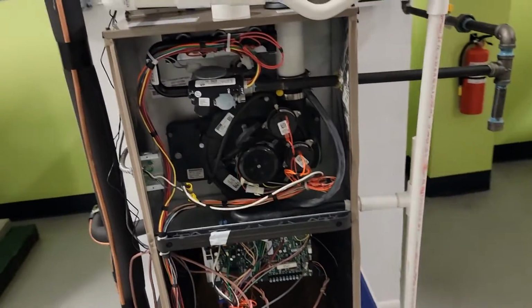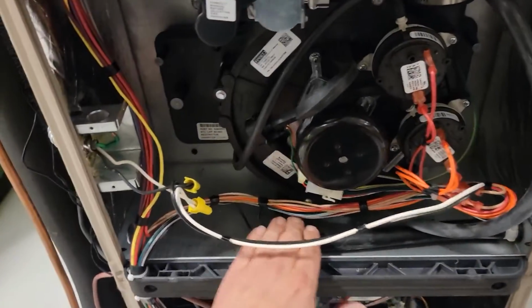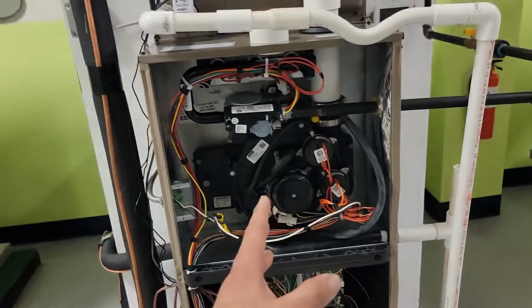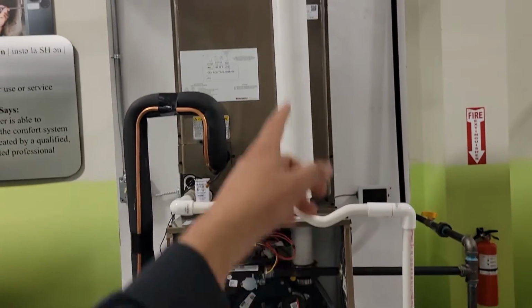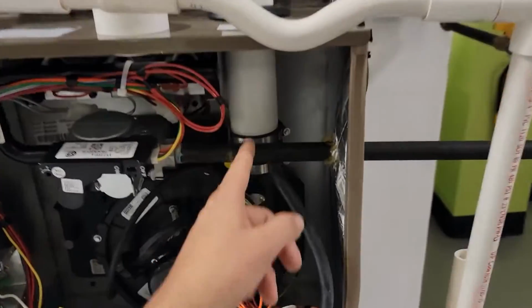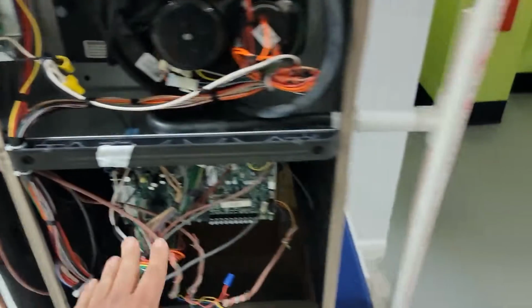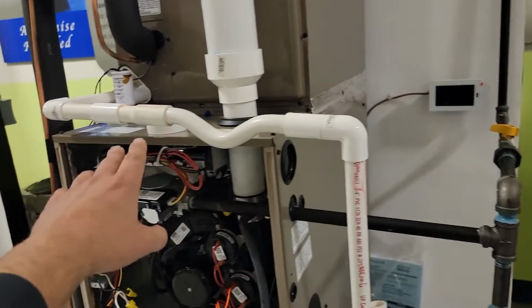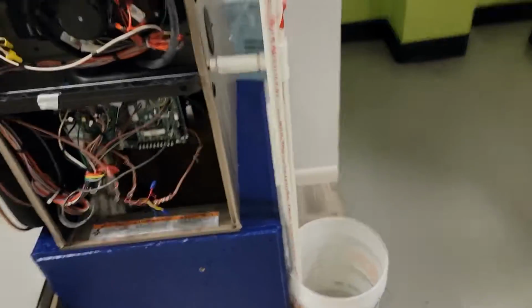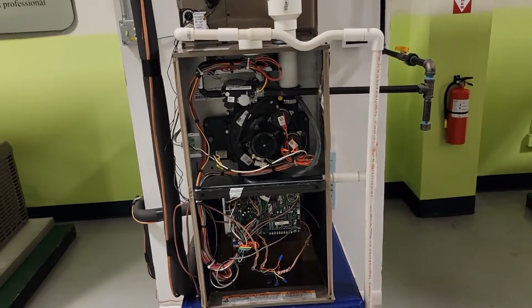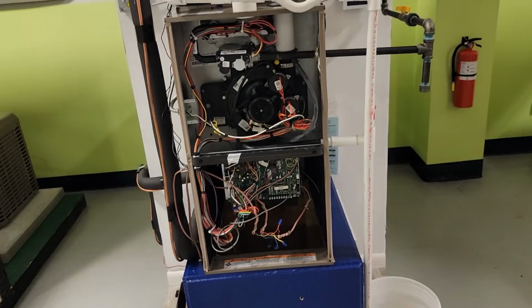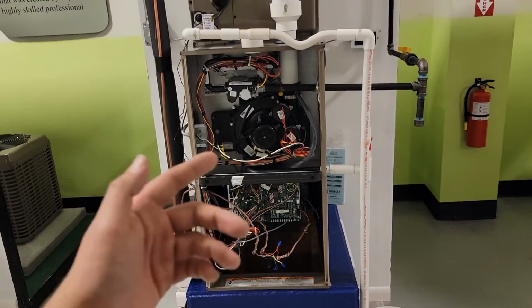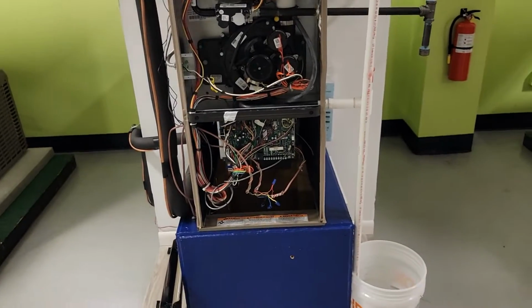This is a 90% furnace. It's a condensing furnace, and one characteristic is the drain right here that comes from this collector box. During its operation, it will create condensate through the exhaust or the flue pipe, and that condensate will come into this inducer assembly housing, and then it will leave via this drain tube right here that comes from the collector box at the very bottom. And then of course it's tied into our condensate drain that leaves our air handler's indoor coil, and then it goes into this bucket, but it would be into your main drain or condensate pump, and it would probably terminate outside. Usually you want to run it to a main drain because, during the winter, if it gets cold enough outside, your drain tube, if you're using 3/8 drain tube, is going to freeze.